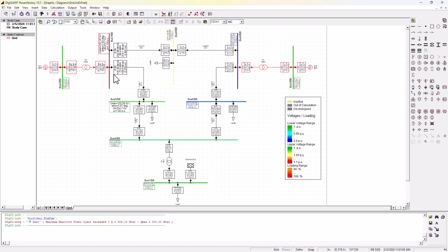So in closing, the takeaway is that if you are analyzing your power system network and you find different voltage levels and voltage swings, this is caused by uneven reactive power sharing between the generators. One is being overburdened by the other, by the system. If we do the droop settings and all other set points, we can eliminate this situation and get our simulation working accordingly. So that is it, guys.